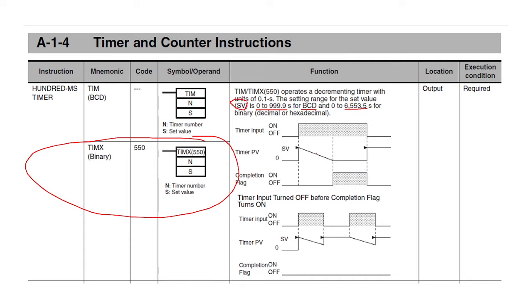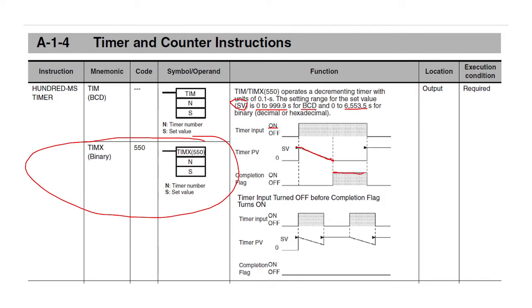A quick overview of the operation of a timer. When the timer input is on, that is, you've pressed the button to activate the timer, the timer will count down the set point like this until it gets to 0. When the set point has reached 0, the complete flag will come on here and will remain on as long as the timer input is active. Then it'll go back to 0 and the timer can run again.